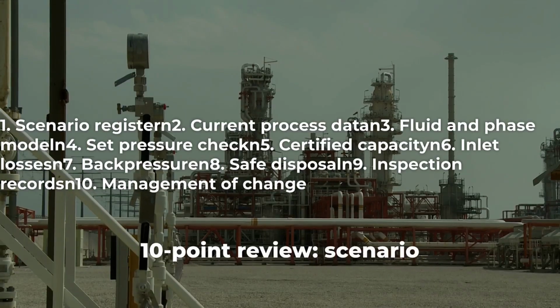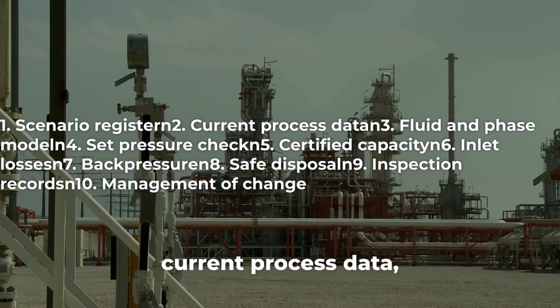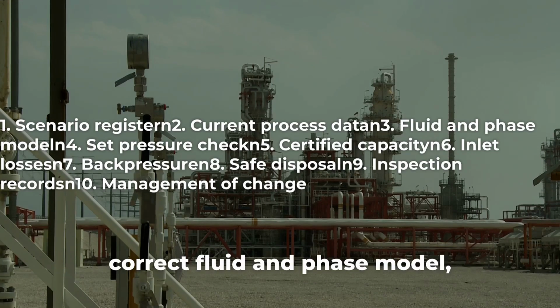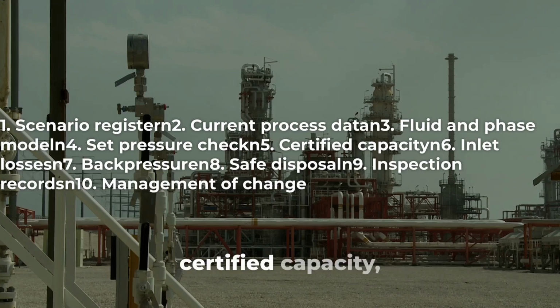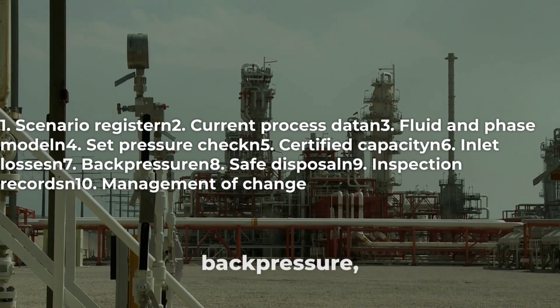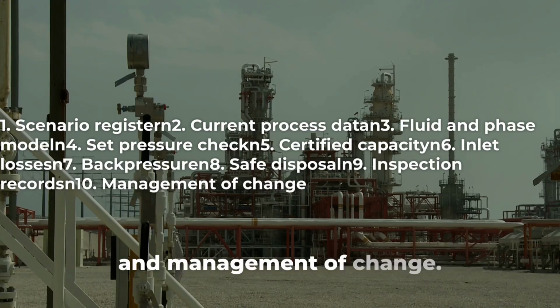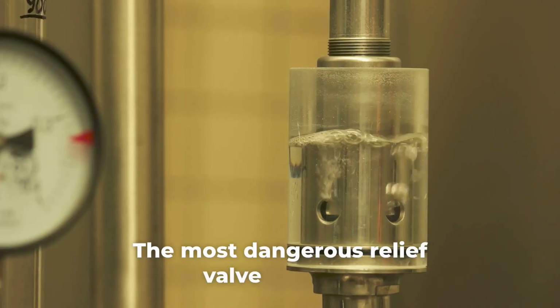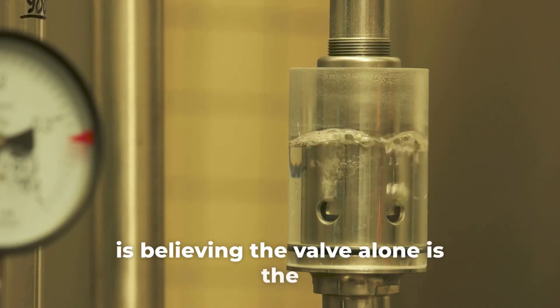10-point review: scenario register, current process data, correct fluid and phase model, set pressure check, certified capacity, inlet losses, back pressure, safe disposal, inspection records, and management of change. The most dangerous relief valve mistake is believing the valve alone is the protection system.